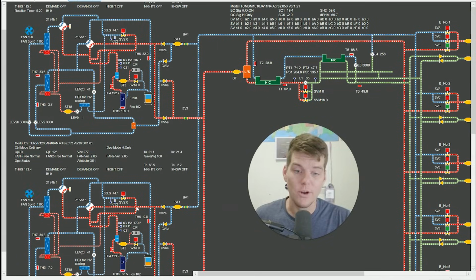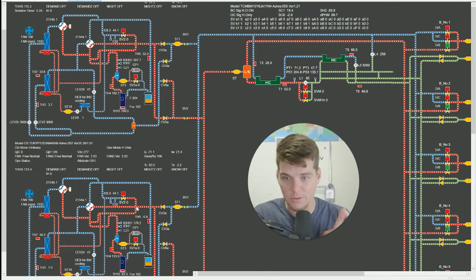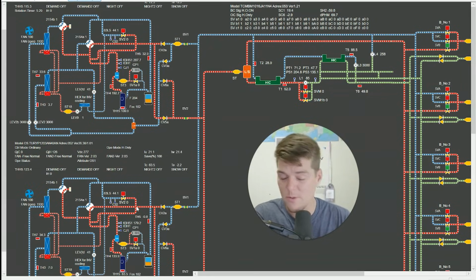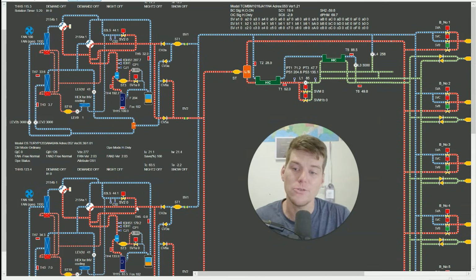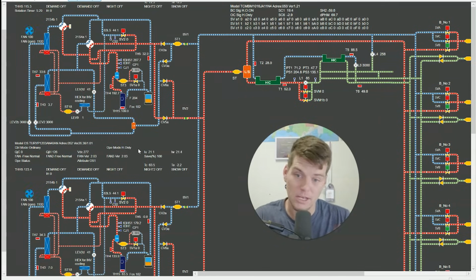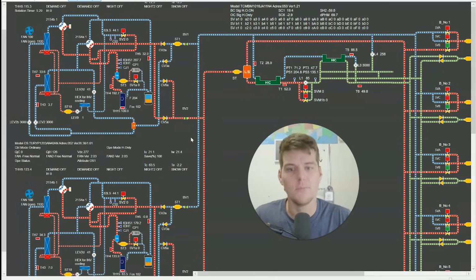We know what now? We know the master module is not getting enough vapor to the compressor. We know that the submodule is getting too much refrigerant to the compressor. Okay, those are two things that we clearly spelled out by completing the triangle. Now, we haven't finished it yet because we don't have subcooling. Well, what would subcooling be?